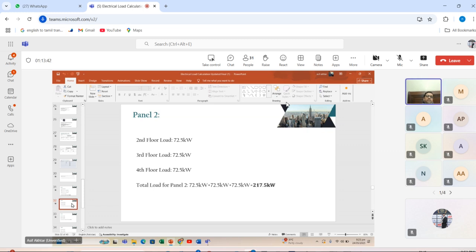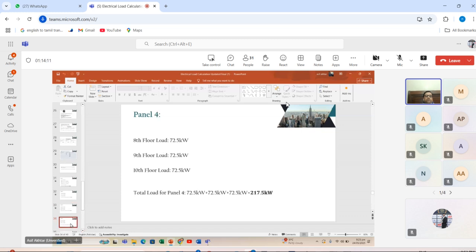In the same way, we do the calculation for the second floor, third floor, and fourth floor. Now we add all these loads, so the panel 2 load is 217.5 kilowatt. In the same way, for panel number 3, the 5th floor, 6th floor, and 7th floor, we add all these and get 175 kilowatt. For panel 4, the 8th floor, 9th floor, and 10th floor load, which is the same as you know, the total load is 217.5 kilowatt.